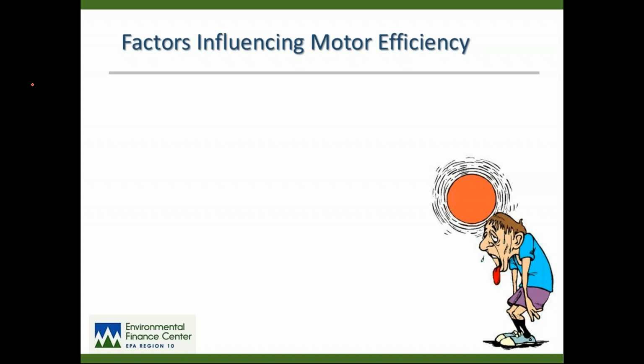Average motor efficiency about 30 years ago was maybe 85 to 90%. Average motor efficiency, especially in the higher horsepowers nowadays, is 94 to 95% efficient. And again, that means 95 cents worth of useful work per dollar spent on energy. There are 7 factors that influence the efficiency of electric motors.